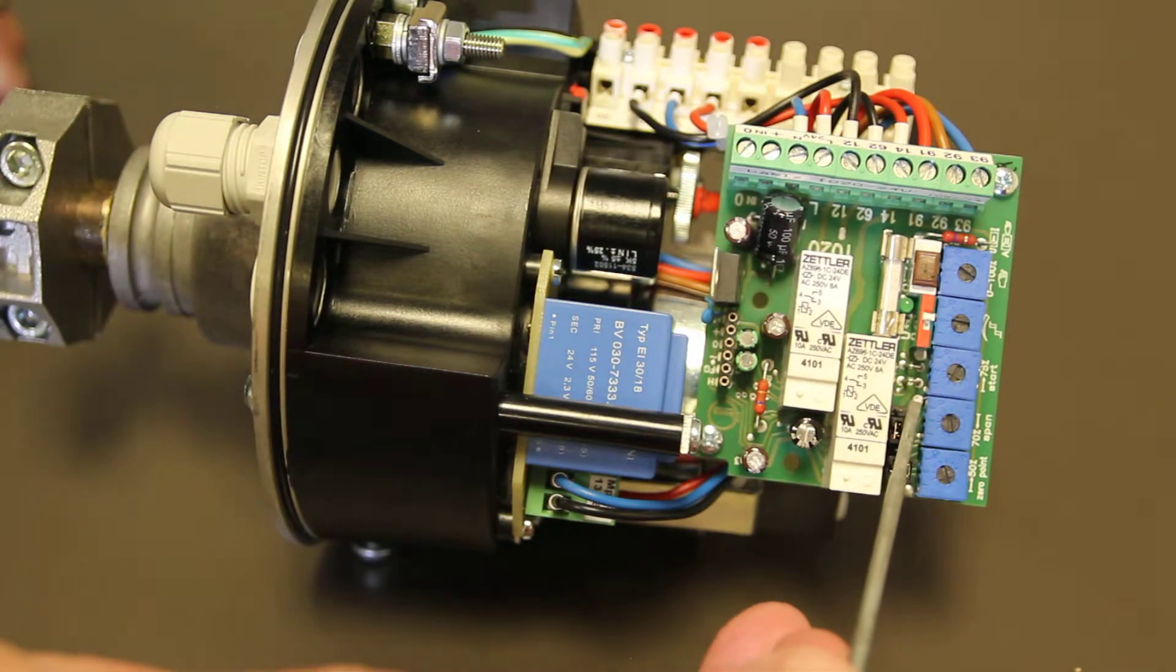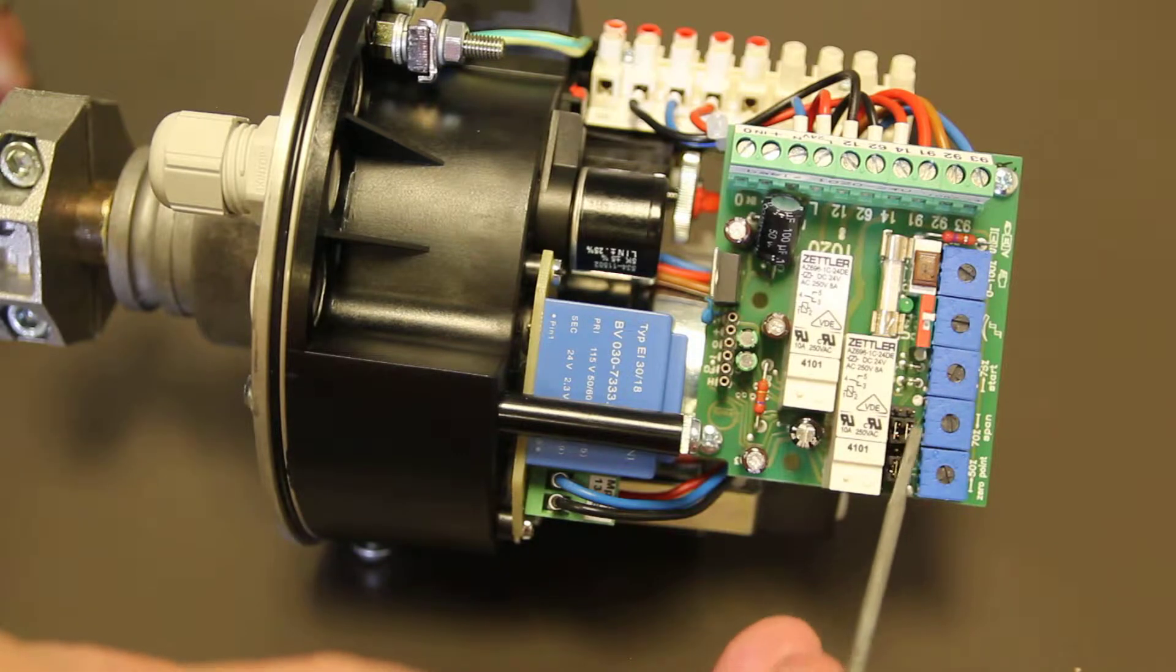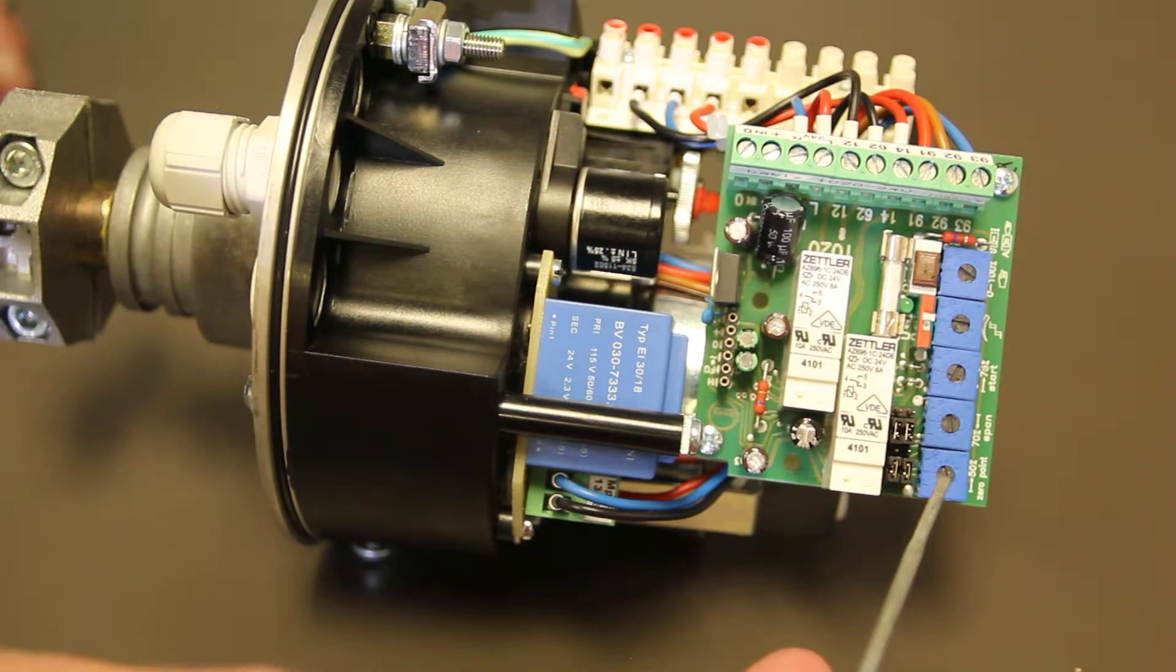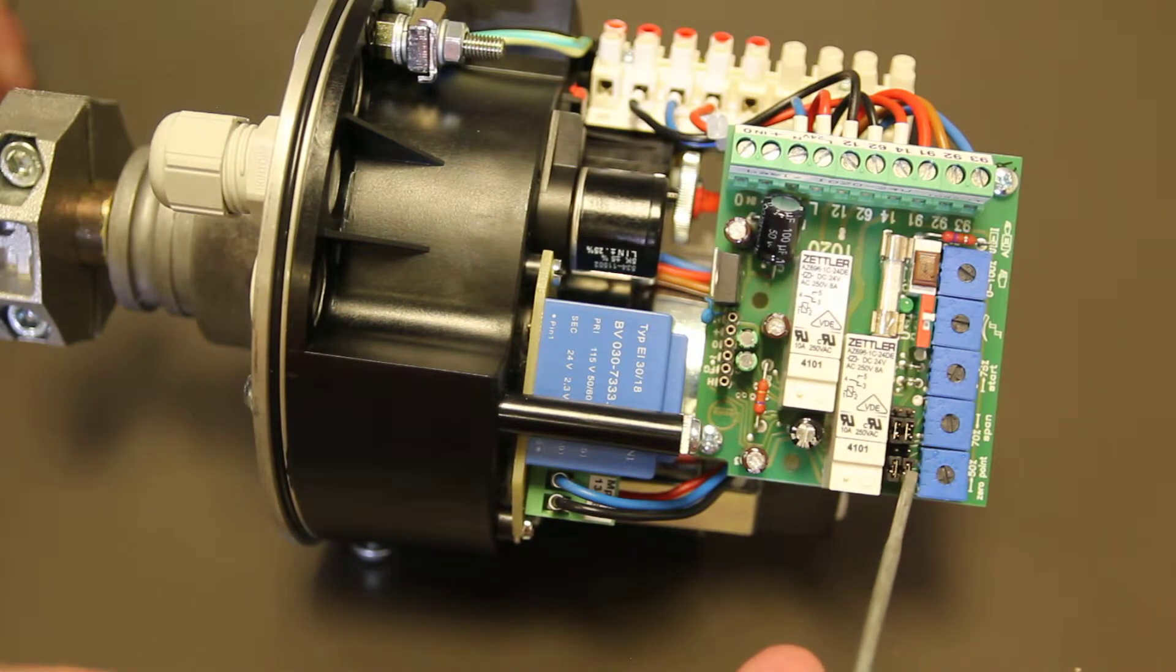On the older models, right here on the servo amp board, the 1020 board, there used to be a manual switch. You could move it from the left side to the right side. In our operating instructions, our main manual for this actuator, it still shows that in one of the diagrams.